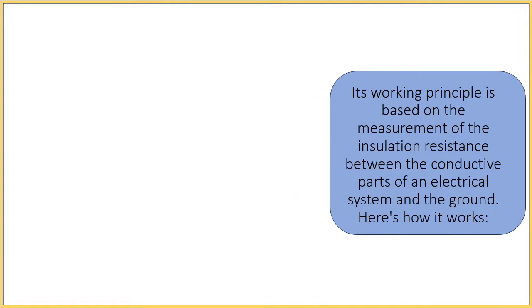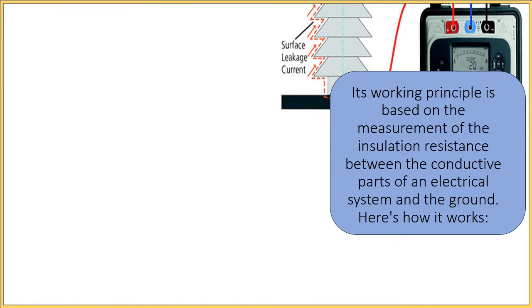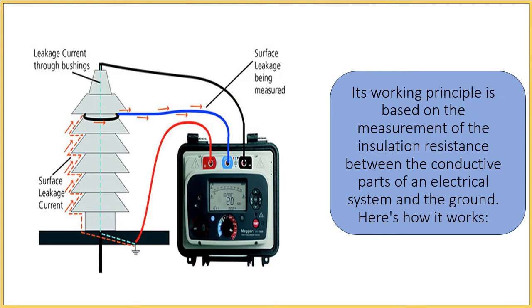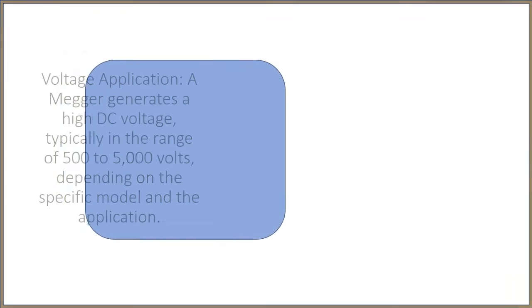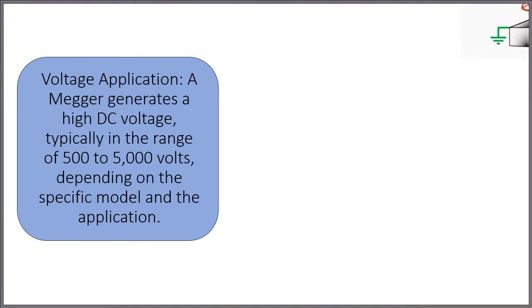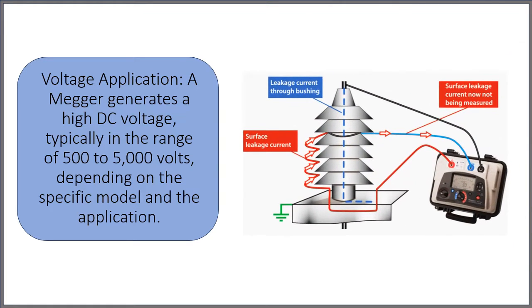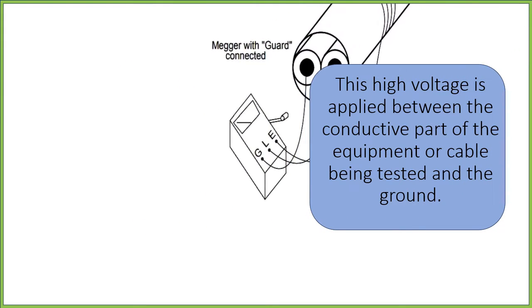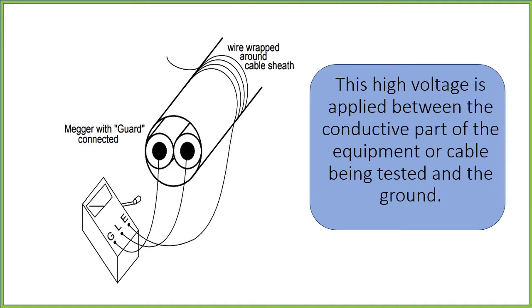Its working principle is based on the measurement of the insulation resistance between the conductive parts of an electrical system and the ground. Voltage application: A Megger generates a high DC voltage, typically in the range of 500 to 5000 volts, depending on the specific model and the application. This high voltage is applied between the conductive part of the equipment or cable being tested and the ground.